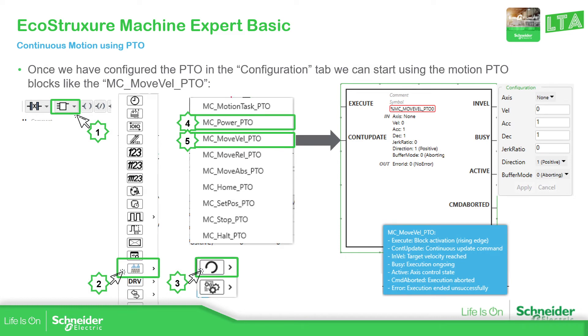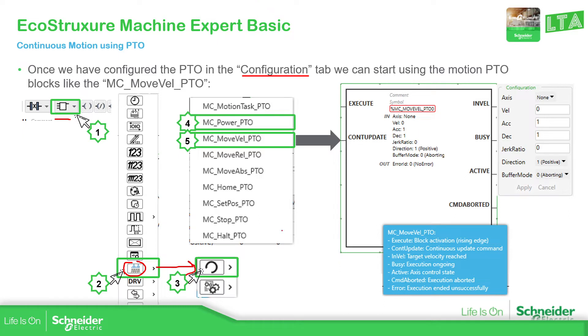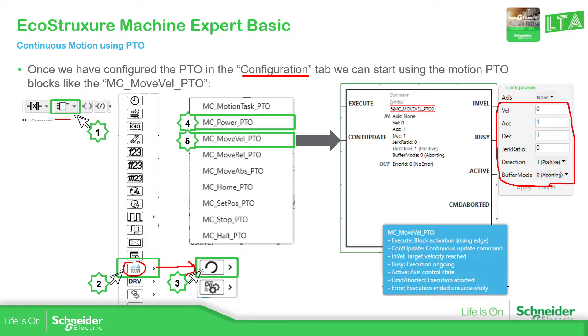So this is good to have it in your HMI in case you want it. So how to use this or how to enable it, you just need to go to the configuration, select from the function blocks the PTO, and then select the one for the motion. We need to add the power and then the move velocity. Once we have the move velocity, these are all the configuration available that we have. And this one is the axis that we have configured on the configuration tab.